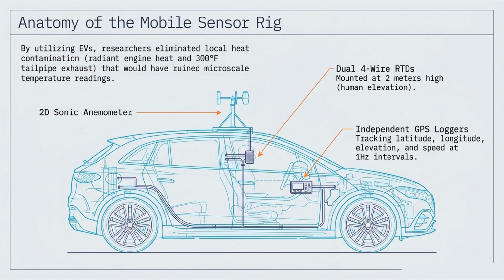For anyone who hasn't dug into sensor hardware recently, what is an RTD? An RTD measures temperature by tracking how electrical resistance changes in a metal element, usually platinum, as the ambient air gets hotter or colder. As the platinum heats up, the electrical resistance increases in a highly predictable linear fashion. That's the basic mechanism, yes.